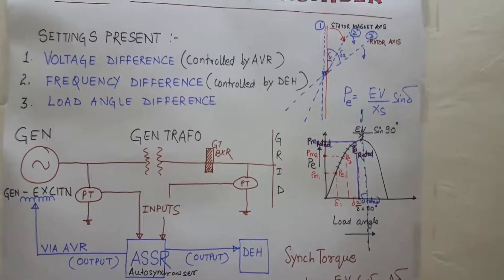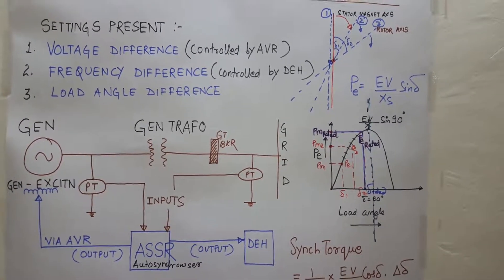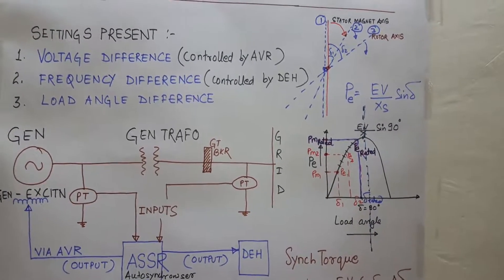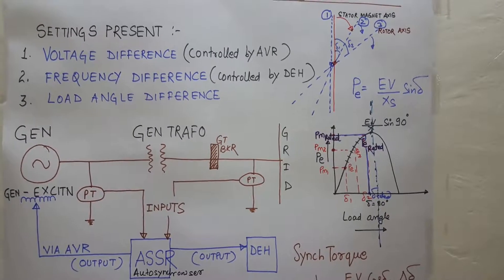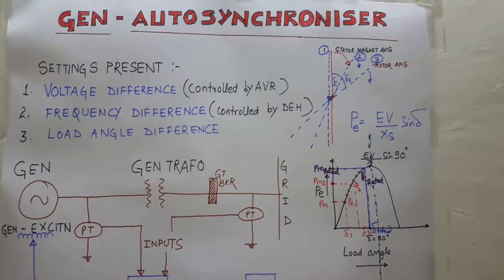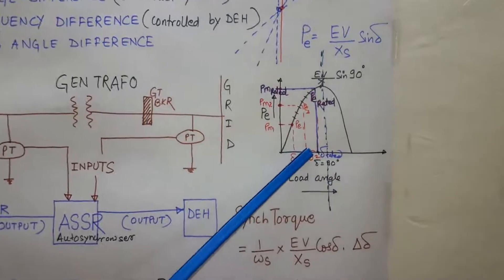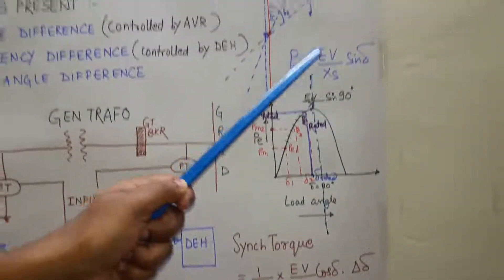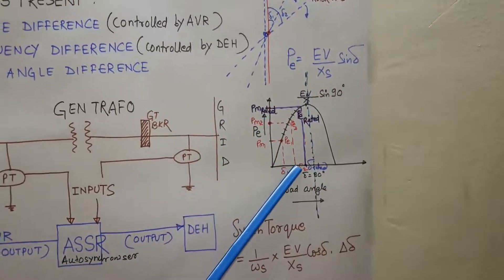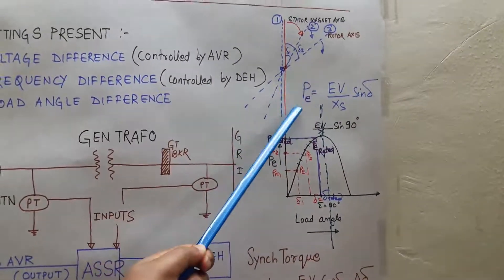After synchronization, the generator will start generating a certain megawatt. Now for generating the rated megawatt it will take some time. At that time the turbine bypass valve is closed and the steam work done is increased, and the delta, this load angle, is shifted towards right side. As we know that power is equal to EV by X sine delta, so by increasing the steam, the delta can be increased, and when the delta is increased, automatically the electrical power will increase.